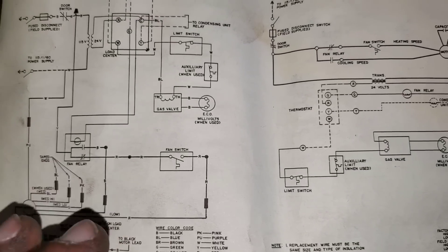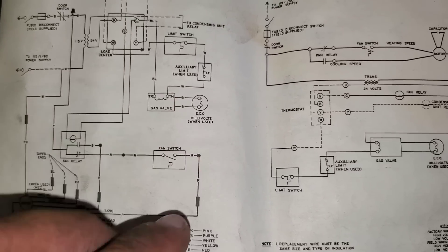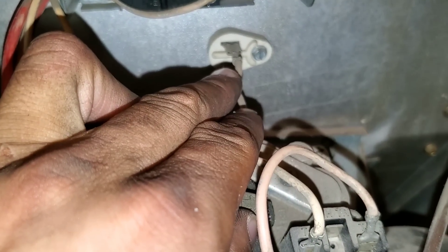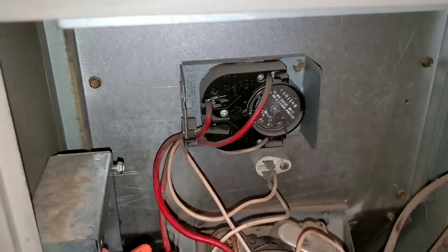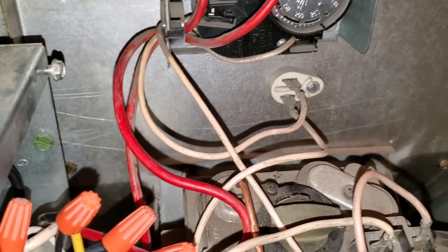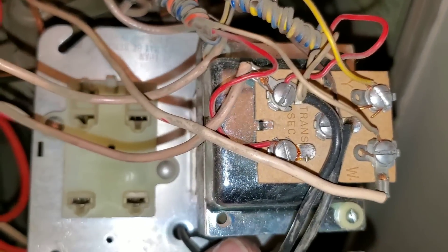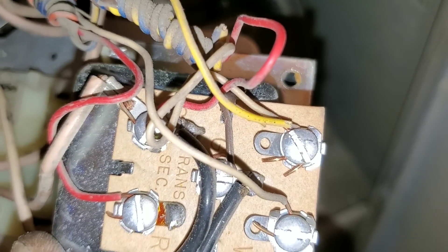We're going to continue in our schematics, keeping it simple, and look at how the limit switch and gas valve tie in. This all ties into our fan switch. This will be our limit switch and this will be our auxiliary limit switch. Looking at the schematics, in parentheses it says 'auxiliary limit when used' — you don't always have this switch. A lot of times they'll stick it right up on top, and you'll have to find and trace the wires. On this one we do have it, so we're going to continue.